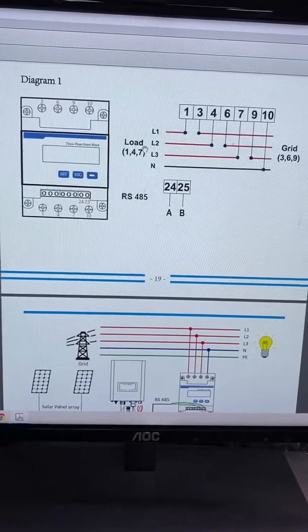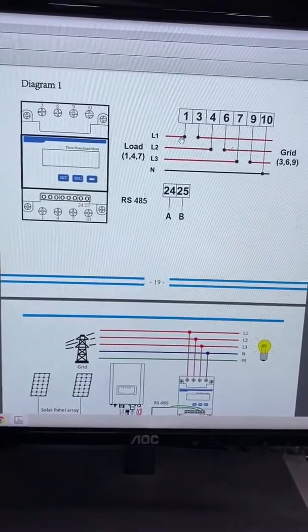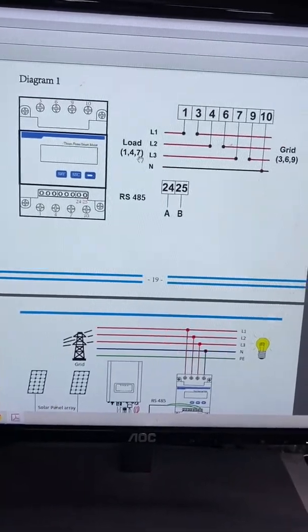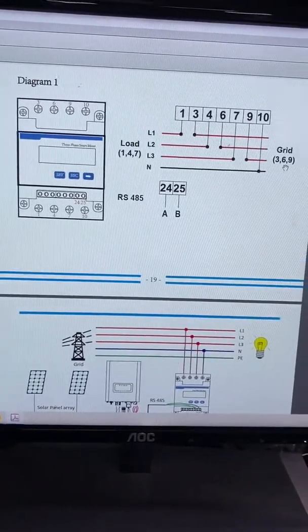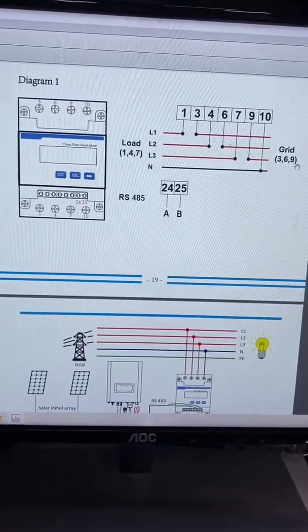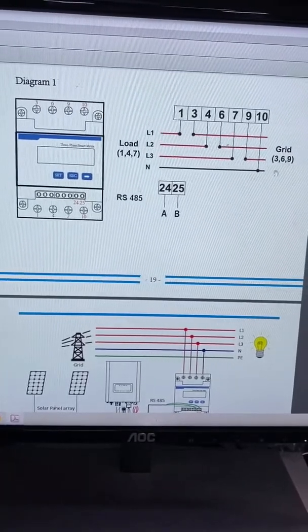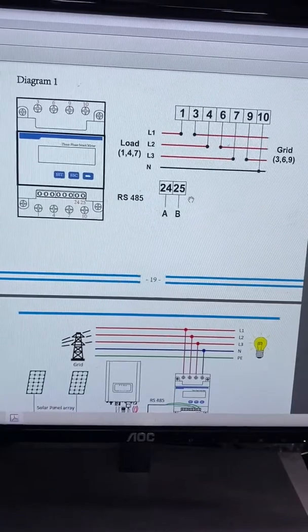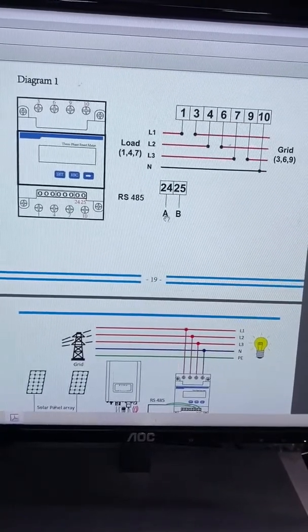Here is the diagram of the energy meter. Terminals 1, 4, 7 are for the load connection. And terminals 3, 6, 9 are for the grid connection. Terminal 24 and 25 are for the RS485 — terminal 24 is for A.